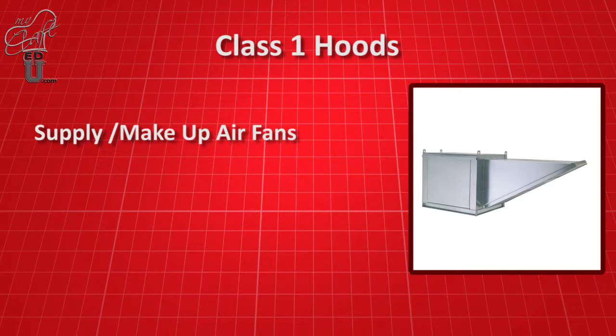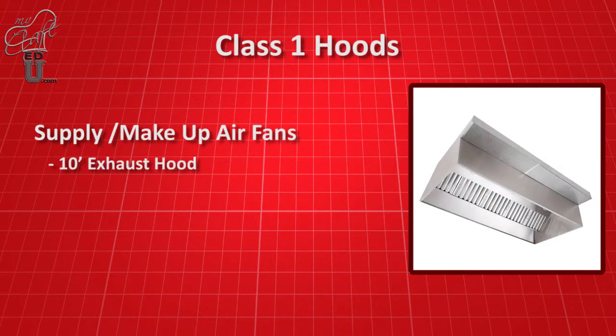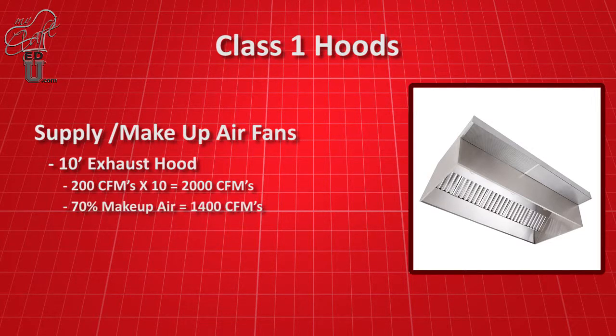Supply fans or makeup air fans are required by International Mechanical Code to be included with hood systems to replace the air that is extracted by the exhaust fan. Supply fans are designed by hood manufacturers to replace 70 to 80% of the exhaust air as a general rule. For example, if your customer has a 10-foot hood and the exhaust fan is rated at 200 CFMs per lineal foot, the total CFMs or cubic feet per minute would be 2,000 CFMs. The supply fans for 70% makeup air would be 1,400 CFMs and 1,600 CFMs for 80% makeup.